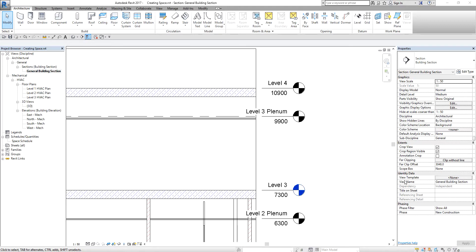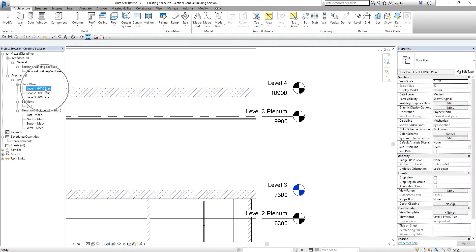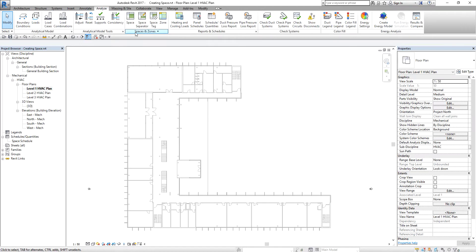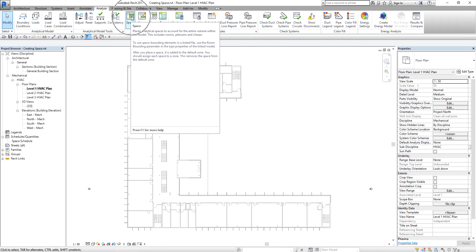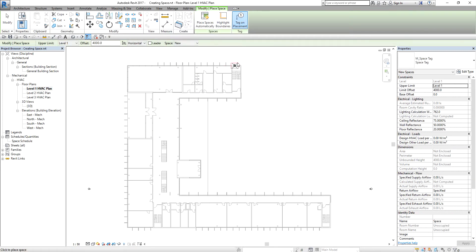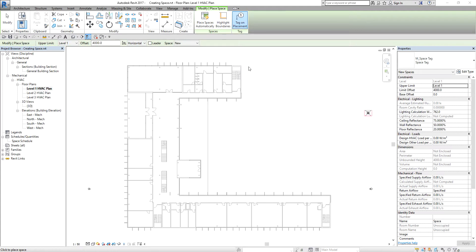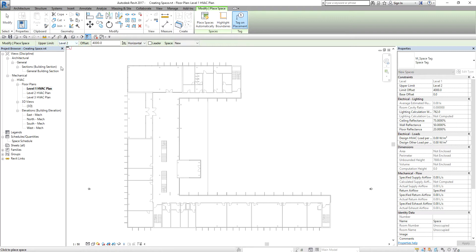Now I'm going to create spaces on the existing levels. I'm going to open the Level 1 HVAC plan and start creating spaces. From the Analyze tab, under the Spaces and Zones panel, I select Space. I'm going to make sure that Tag on Placement is toggled on so that every time I place a space, there's a tag on it. Since I'm on Level 1, I want to create a space from Level 1 to Level 2, so I select Level 2 with no offset — just 0.